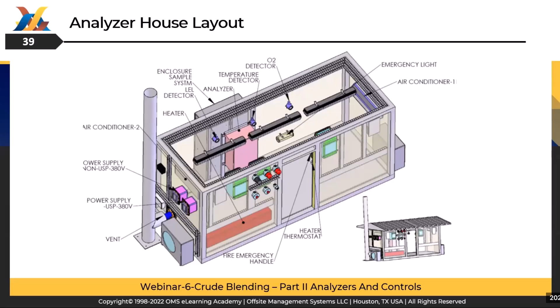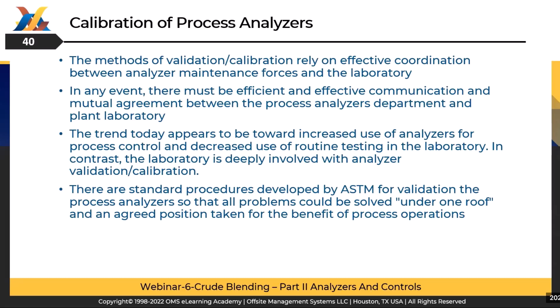When a new process analyzer is initially installed or after significant maintenance has been performed, a set of tests must be performed to demonstrate that the analyzer meets the manufacturer's specification. These diagnostic tests may require that the analyzer be adjusted to provide predetermined output levels for certain certified reference materials, so-called etalon materials, or be compared with other reliable analyzers, such as analyzers present in the laboratory. The methods of validation and calibration rely on effective coordination between the analyzer maintenance team and the laboratory. So there must be effective communication and mutual agreement between the process analyzer department and the plant laboratory. And it's always better to do it during the commissioning or even before. Next slide, please.